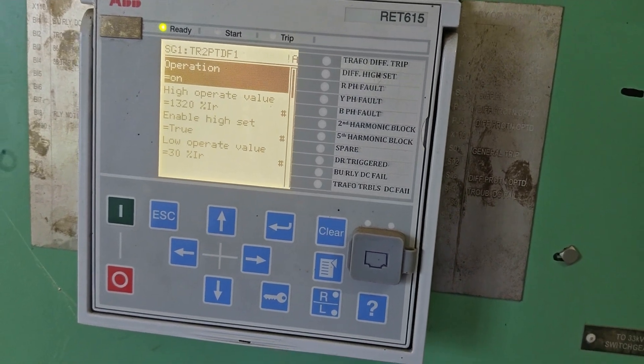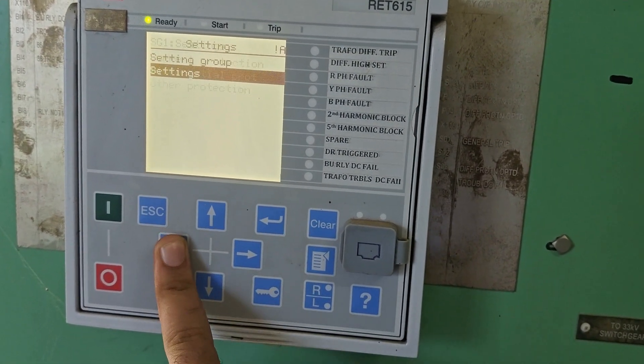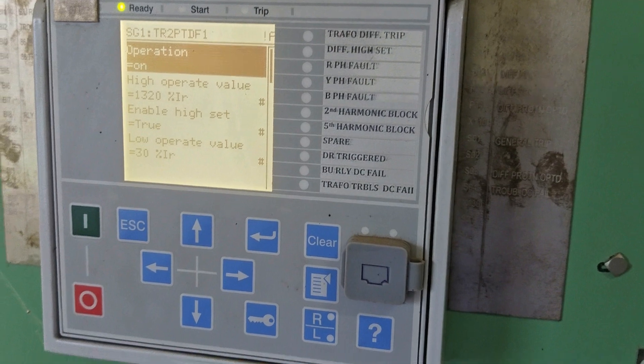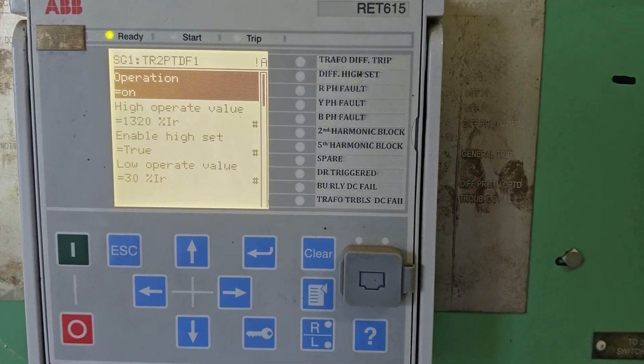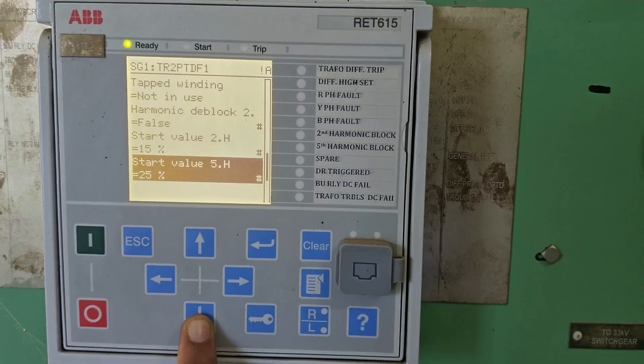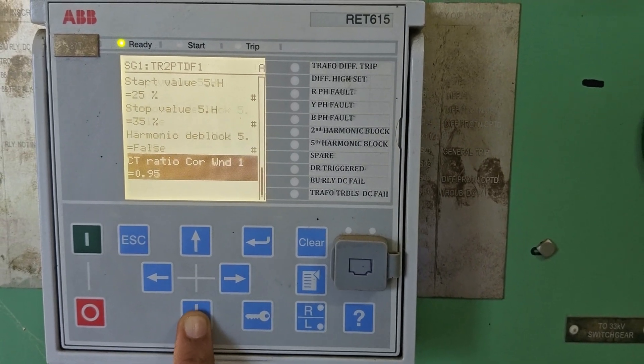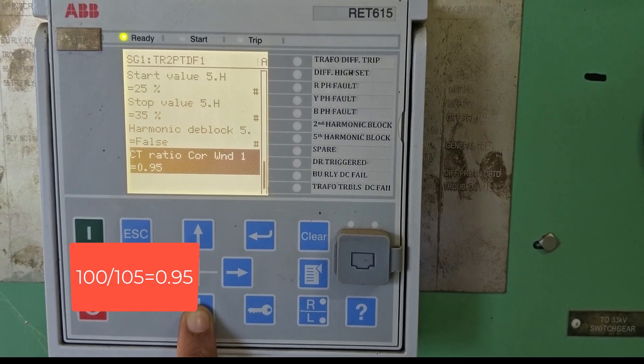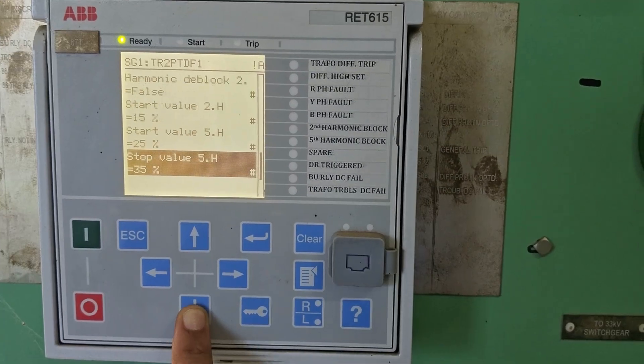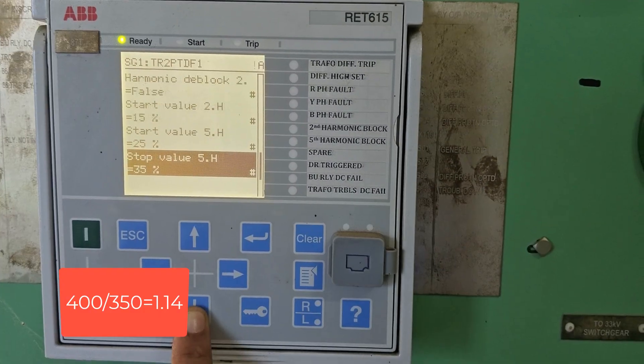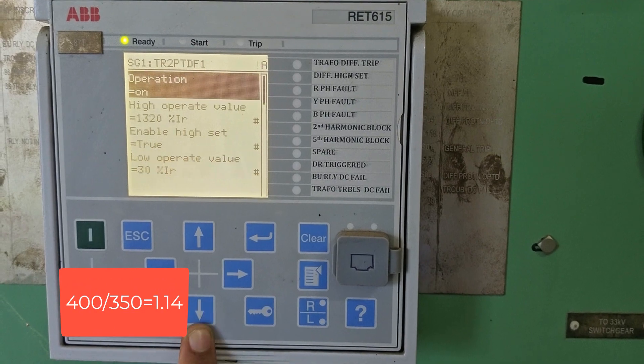For the current ratio calculation: this relay is connected to a 20 MVA transformer. On the primary side, the CT is connected for 100 A and the full load current is 105 A, so 100 / 105 = 0.95 — that is the set value. On the secondary side, the full load current is 350 A for a 20 MVA transformer and the CT connected is 400 A, so 400 / 350 = 1.14.